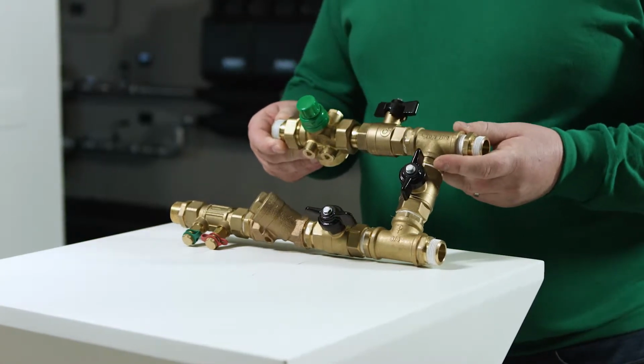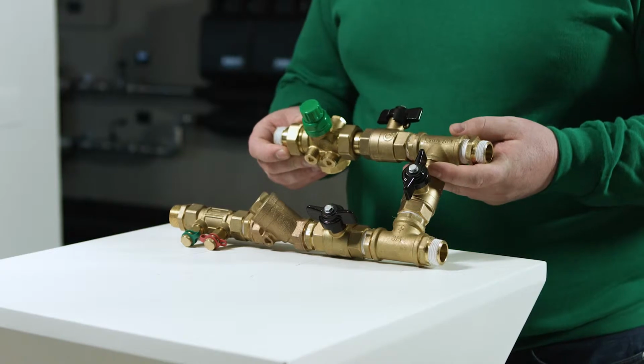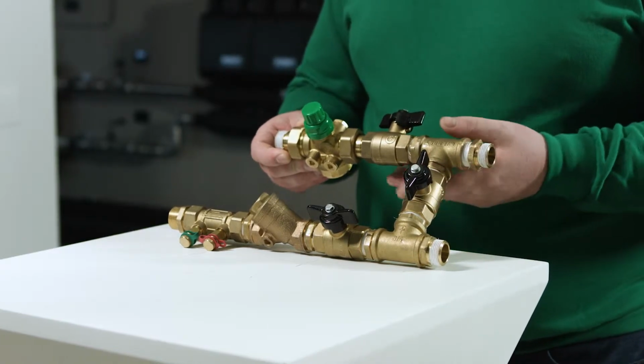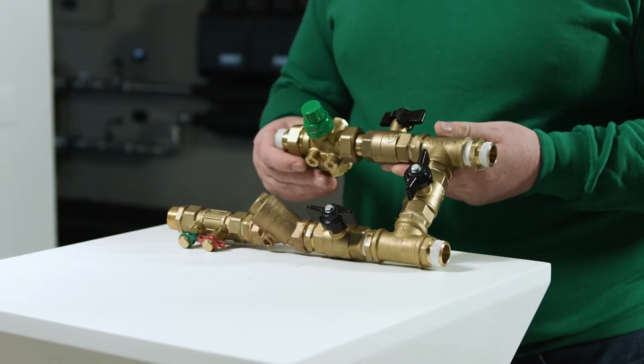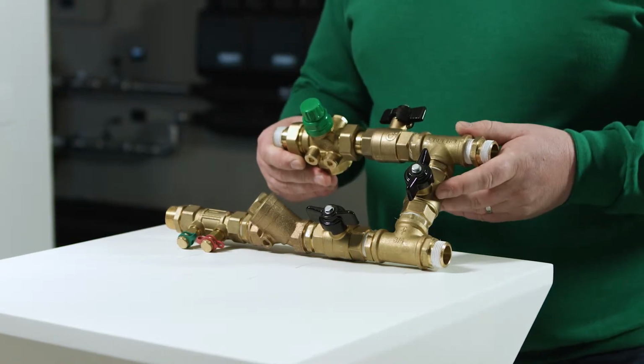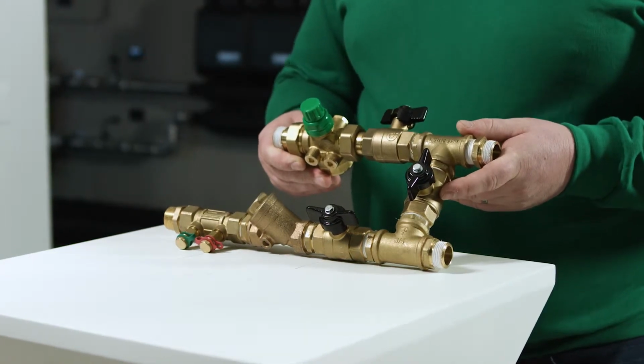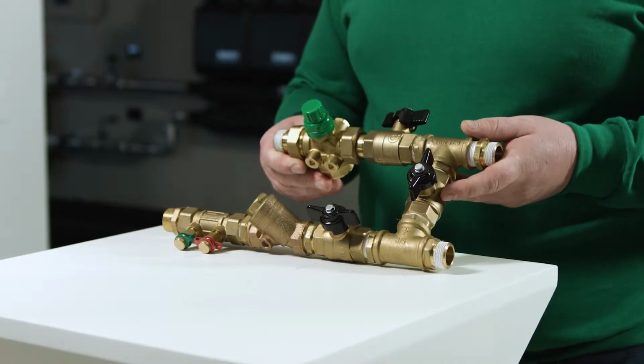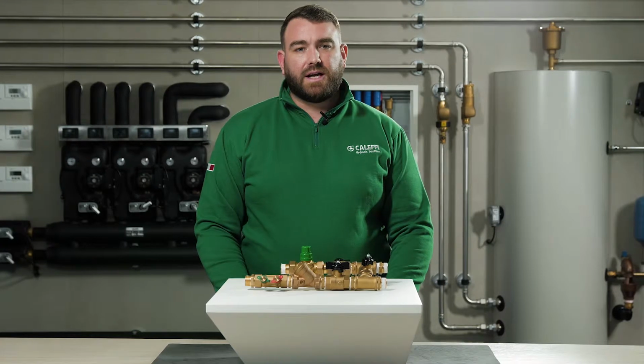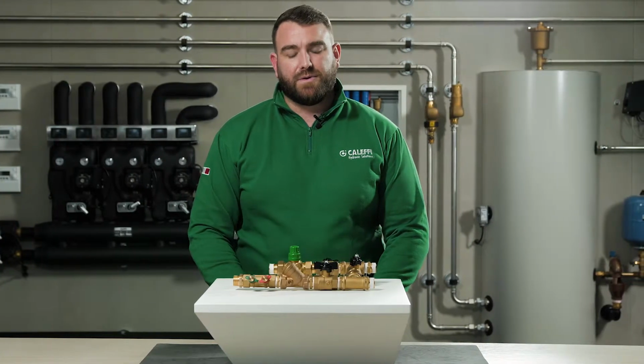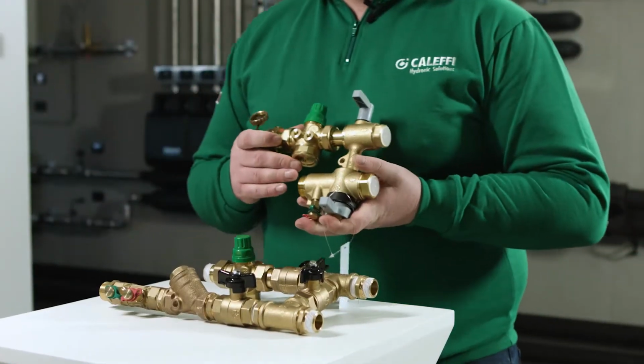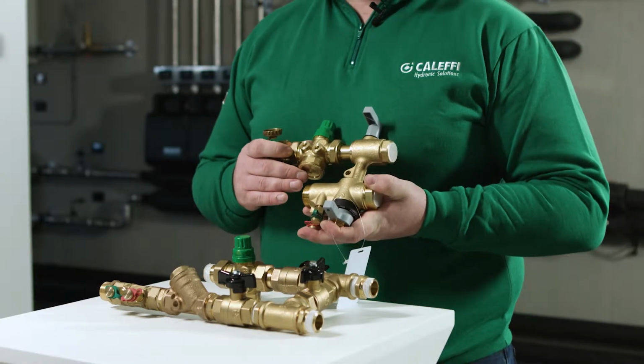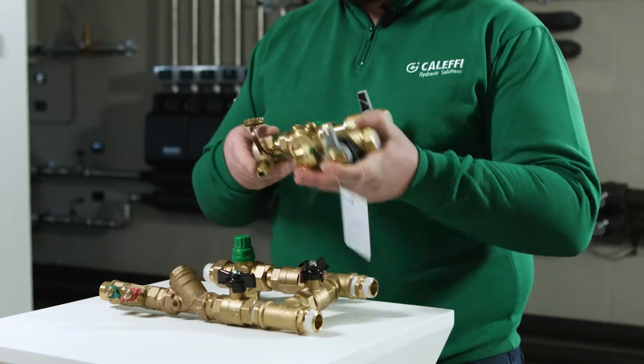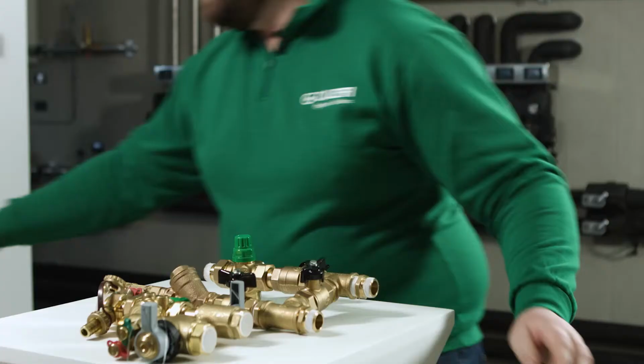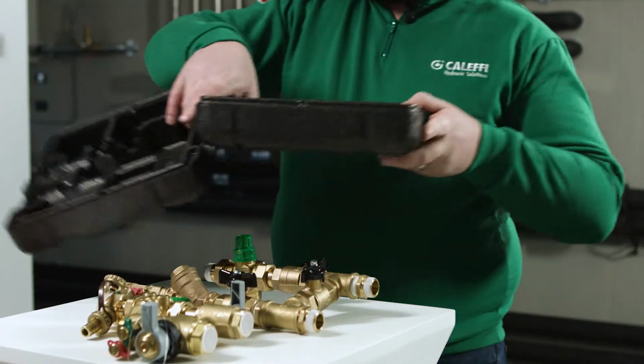Once this process is complete, we have to regulate the flow for each terminal unit. This is achieved by selecting the correct valve set point on the PICV. Due to the complex functions and requirements, we must use a series of different components to enable us to achieve the correct outcome. To simplify the life of the installer, it's possible to use a connection regulation kit for HVAC terminal units. This kit contains all of the necessary components for the commissioning and maintenance of HVAC systems. The unit comes fully insulated and ready for installation.